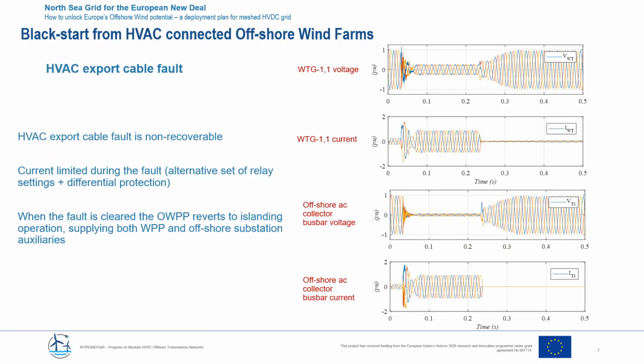These results show the operation of the wind farm during an export cable fault. The first two traces show the voltage and current of one of the wind turbines, and the bottom two, the voltage and current at the offshore collector bus bars. The grid-forming wind turbines keep the current control during the fault, and once the fault is cleared, the wind turbines will recover the system voltage in about 50 milliseconds. This is an important behavior, as now the wind turbines are the only grid-forming equipment in the system, and therefore are in charge of voltage recovery after the fault.